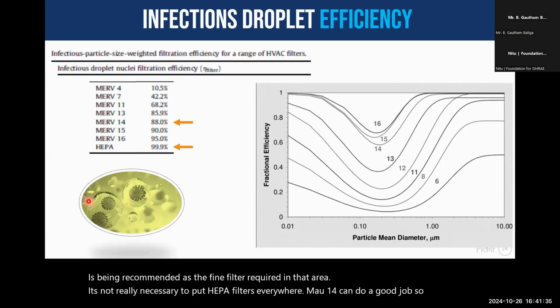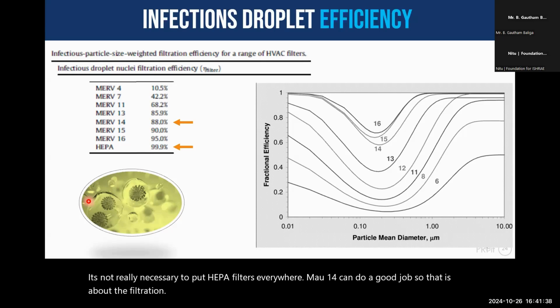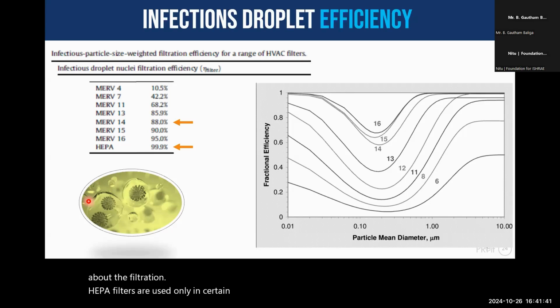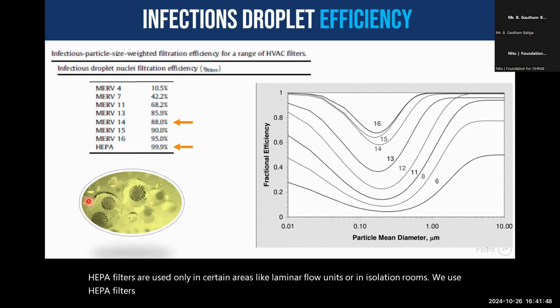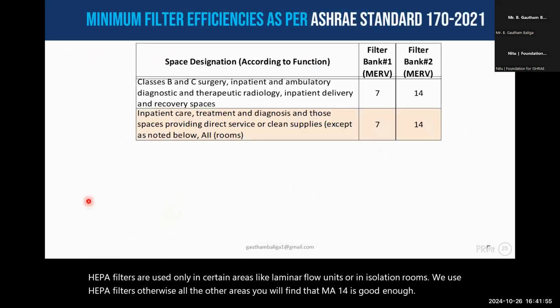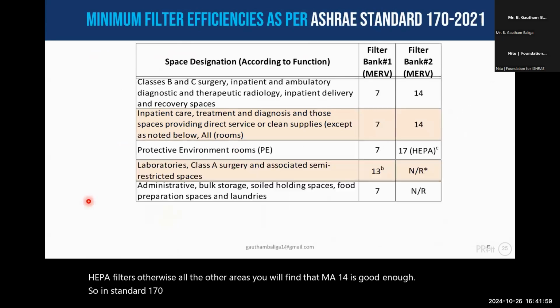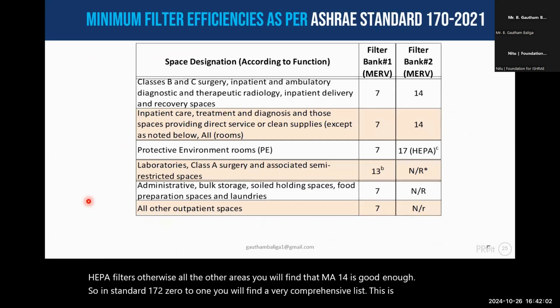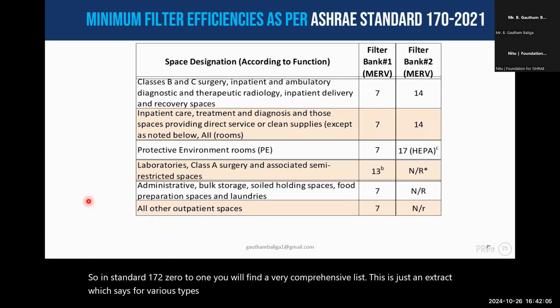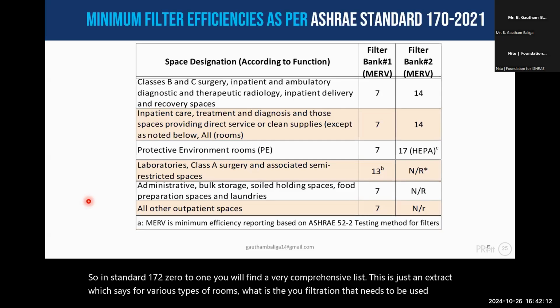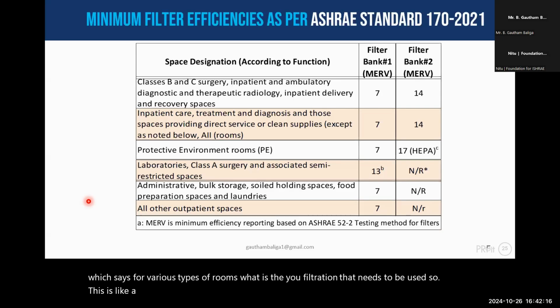So that's about the filtration. HEPA filters are used only in certain areas, like laminar flow units or in isolation rooms. We use HEPA filters. Otherwise, in all the other areas, you'll find that MERV14 is good enough. So in standard 170-2021, you'll find a very comprehensive list. This is just an extract which says for various types of rooms, what is the filtration that needs to be used. So this is like a prescription. You have a room, which filtration to be used in that particular room.